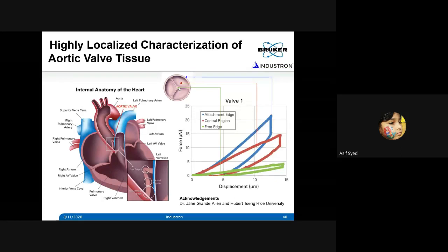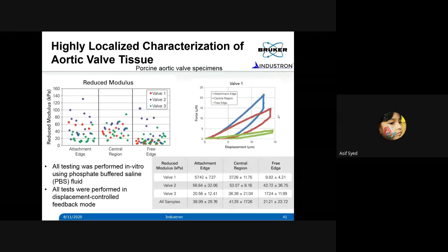That's what you see on this load displacement curve. You can readily see that at the edge, for a given penetration, let's say 10 micron, you require more load to penetrate 10 microns or higher depths. So the edges are stiffer compared to the middle and the end. This is how it's supposed to be. At the middle it is less stiff than the edge, and at the end it is very soft compared to the rest of the regions. We can do a number of tests, it's very repeatable, and then you can see the properties in terms of modulus.